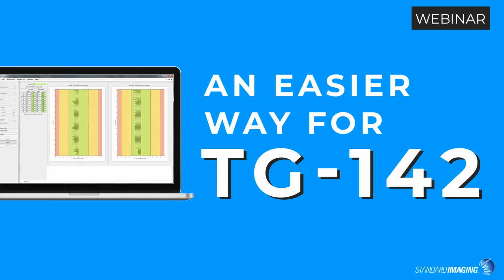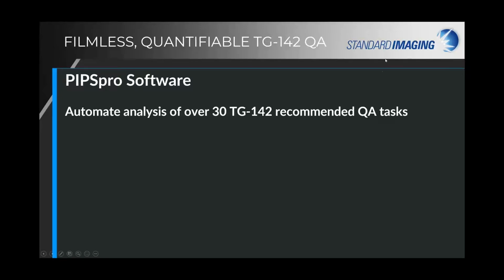Anyway, today I'm here to talk about PIPSpro, which is what we call our TG-142 solution. And basically, it automates the analysis of over 30 TG-142 recommended QA tasks. And that includes, let's see, my PowerPoint is taking a break. There we go. Sorry.